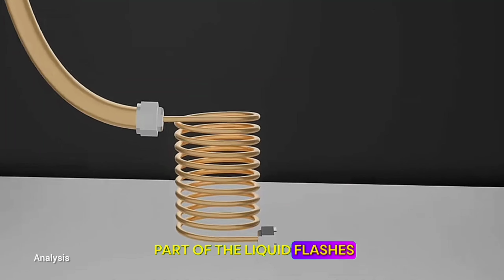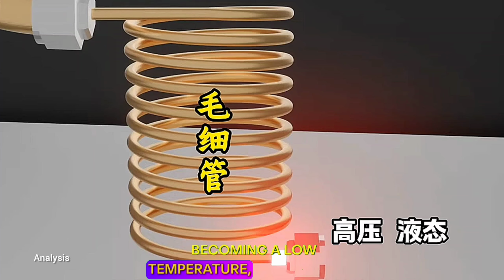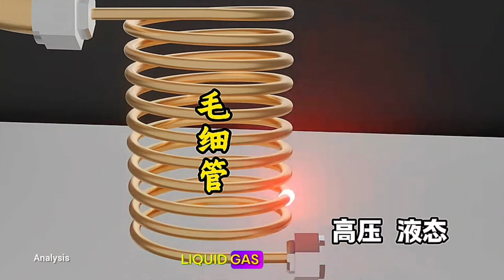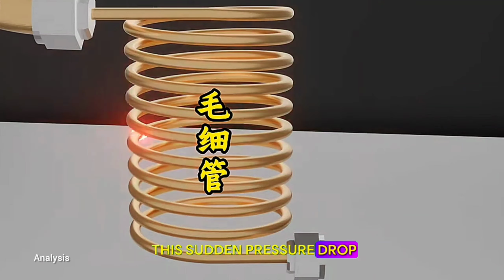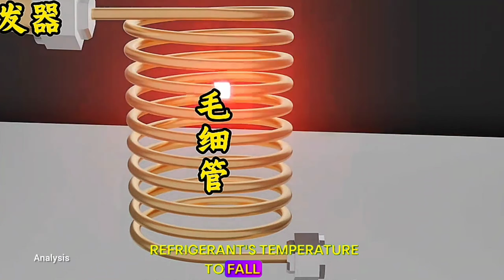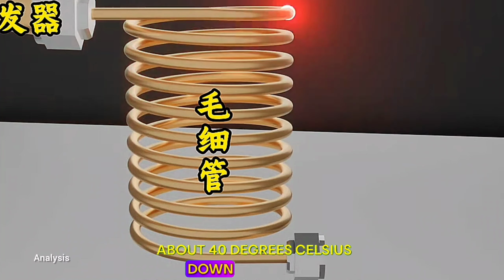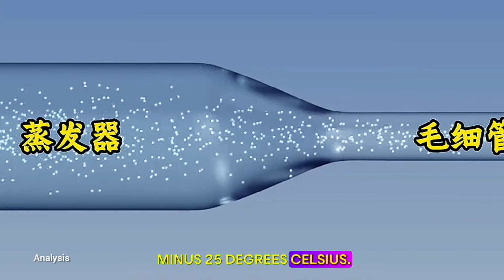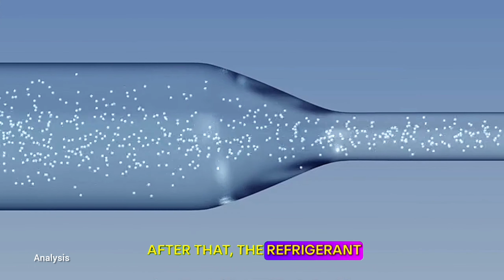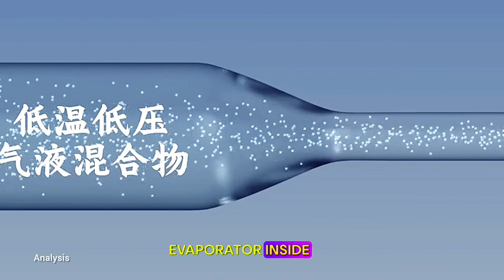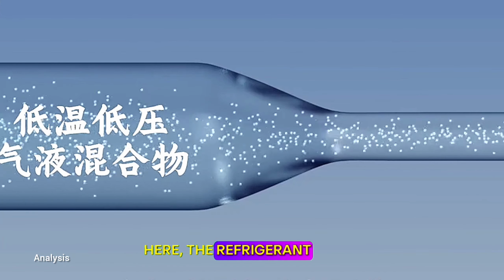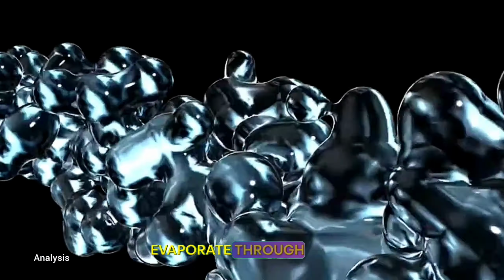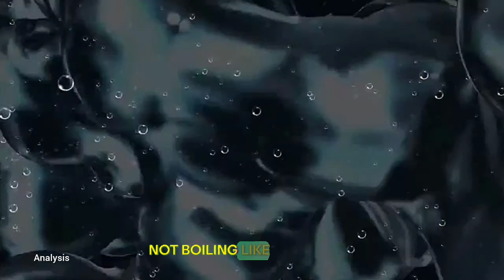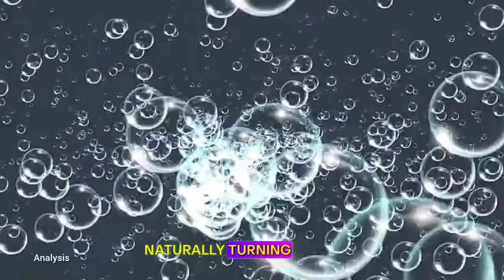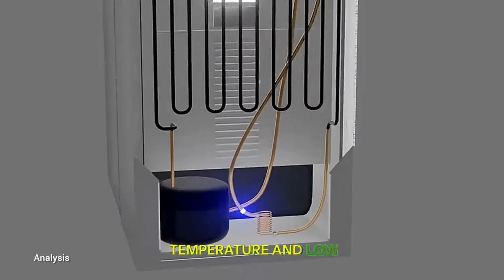Part of the liquid flashes into gas, becoming a low-temperature, low-pressure liquid-gas mixture. This sudden pressure drop causes the refrigerant's temperature to fall from about 40 degrees Celsius down to around -25 degrees Celsius. After that, the refrigerant enters the evaporator inside the refrigerator. Here, the refrigerant begins to boil and evaporate through direct cooling, not boiling like on a stove, but naturally turning into gas under low temperature and low pressure.